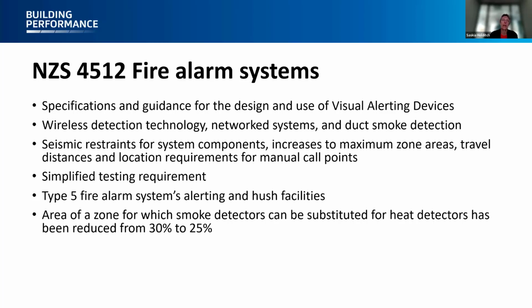Some testing requirements have been made easier to comply with. The Type 5 system, where apartment units and sleeping areas have a specific alarm type system, has been updated to keep with the latest trends and developments. There are also features where smoke detectors can be substituted for heat detectors in commercial buildings, not just houses. This helps with false alarms in dusty environments like manufacturing plants. If the acceptable solution requires smoke coverage, you're allowed to replace a number of smoke detectors with heat detectors, but that's up to 25%. It's not expected to have a big impact on nuisance alarms in commercial buildings.